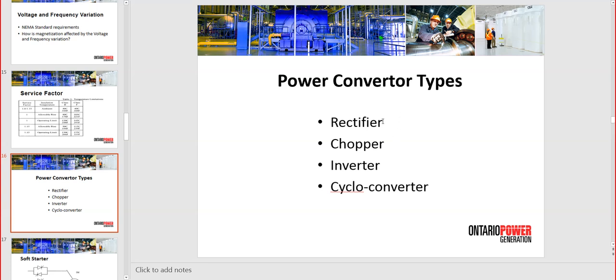There are 4 in total. In the power electronics that can be used with motors, and in the actual drives, we can have rectifiers, which are the DC drive for DC motors. You have a rectifier that controls the speed of a DC motor by controlling the voltage on the shaft, on the actual armature.